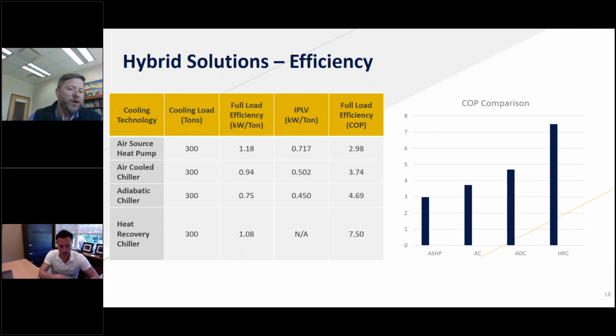And now if I can use the chilled water and the hot water for a 4-pipe building, we see COPs that were maxed out at, you can see, 4.7 become 7.5. We have COPs that get as high as 9 when you look at the combined COP, right? Because for every unit of energy in, we get the output that is the cooling, and we get the output that is the heating. So that one energy input gives us 2 different uses of output, but we get to add those together, and we get really, really efficient. And so on the right hand side, it's just a bar graph that's comparing the different COP of the units depending on how we're designing that.